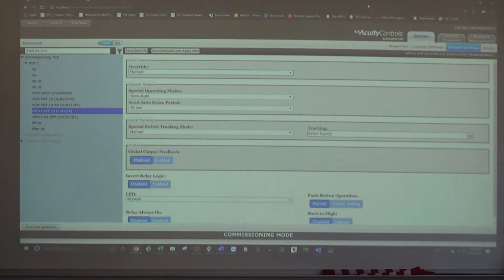So if you change that to override off, can you disable the switches, like in that cafeteria example? You cannot disable the switch, you only disable the occupancy sensors, and you change the default behavior. Let's say the system was on, the switch was on, and you power cycled the circuit. It would come back in its default state, which would be off, and then you'd have to hit the switch to turn it back on. How would we get rid of that switch then? I will get to that.